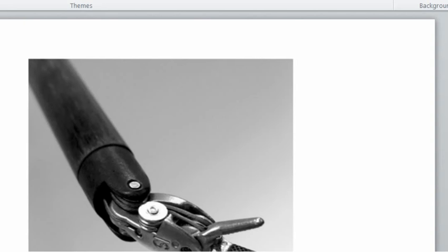So, number four would be to locate the sensor at the instrument tip, such as on the gripper jaw. Instruments which are equipped with a gripper offer the additional possibility of integrating a force sensor in the gripper. The jaw is the place where force acting at the surgical instrument tip can be measured most directly. Friction and other disturbance forces generated from any moving mechanisms do not affect the measurements of the tissue contact force as much as in the other cases.